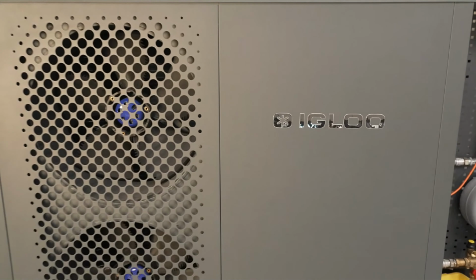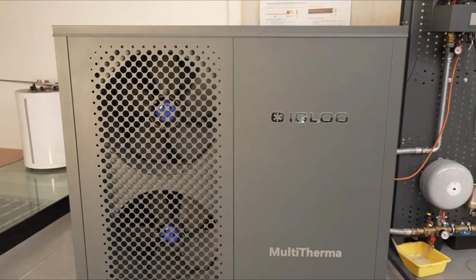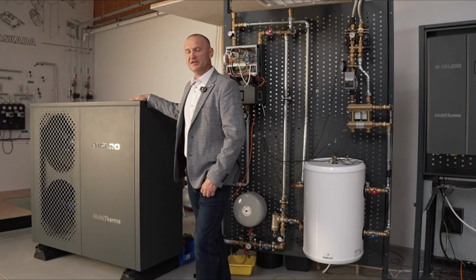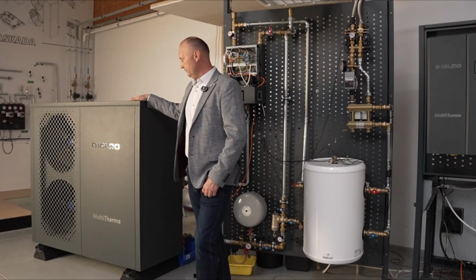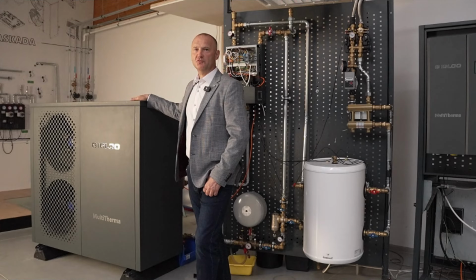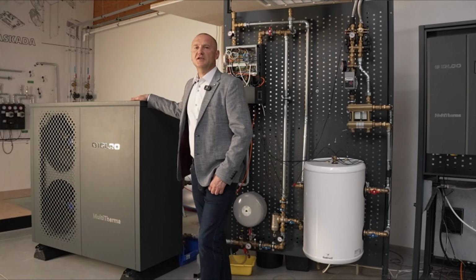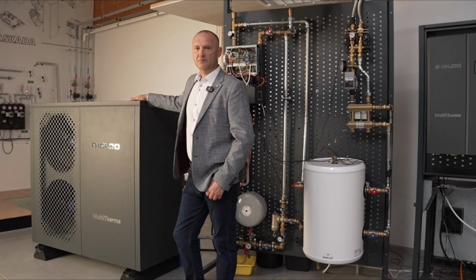MultiTherma is an advanced inverter heat pump. It is specifically a monoblock type heat pump, where the fundamental function of this unit is naturally heating. However, our heat pumps are also capable of cooling, as they operate in a fully reversible mode and can additionally supply us with chilled water for various air conditioning systems.